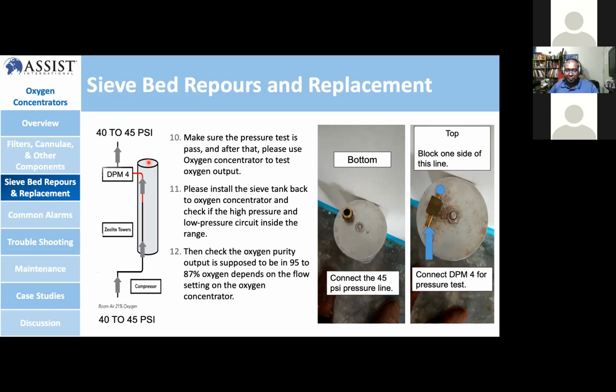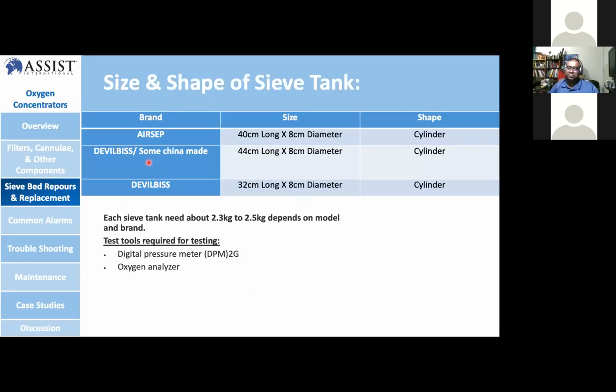So what you need when you do sieve tank replacement of zeolite: you need to know the size of the cylinders, and very important, you need 2.3 kilo to 2.5 kilo of zeolite, depending on the model and the brand of zeolite. The test tools are the digital pressure meter, DPM4, and an oxygen analyzer. And you need an air compressor. If you don't have one, you can use your oxygen concentrator's air compressor as well. But if you have a separate air compressor, that'll be good actually.